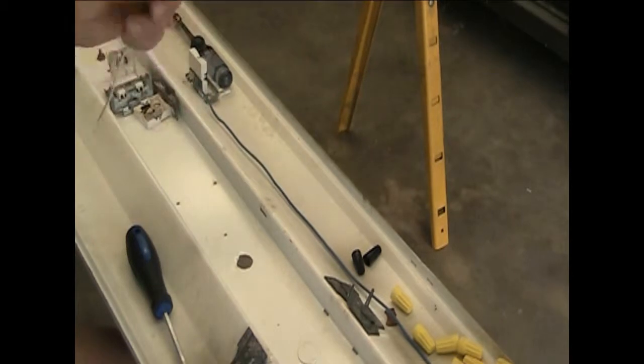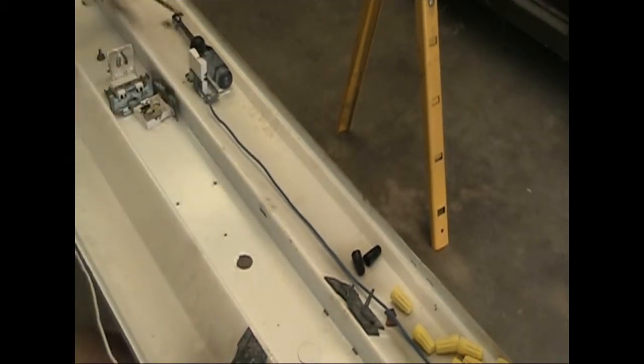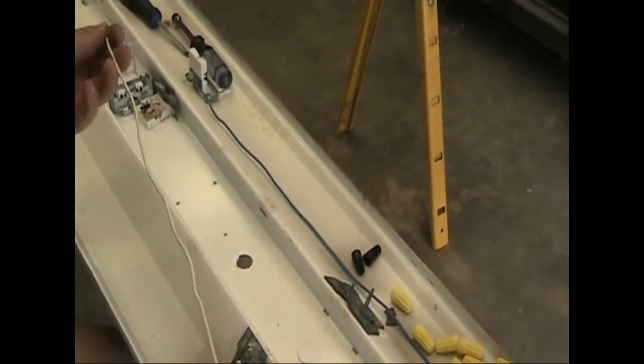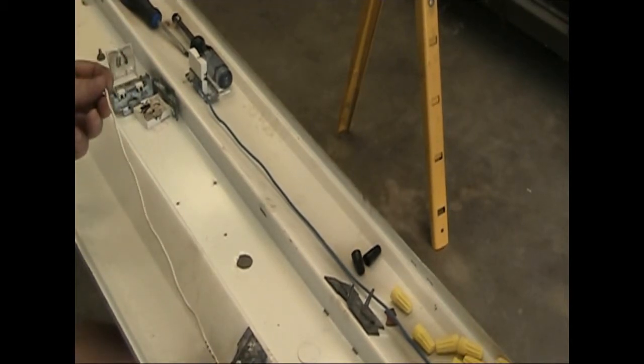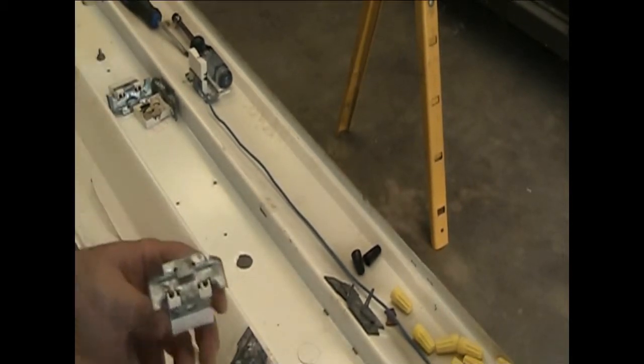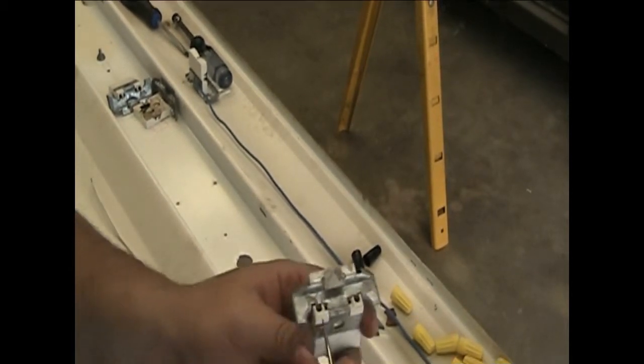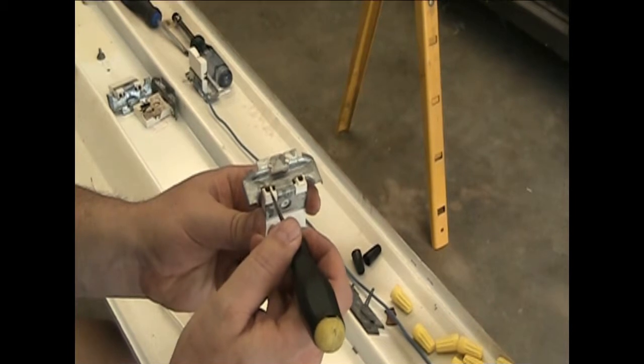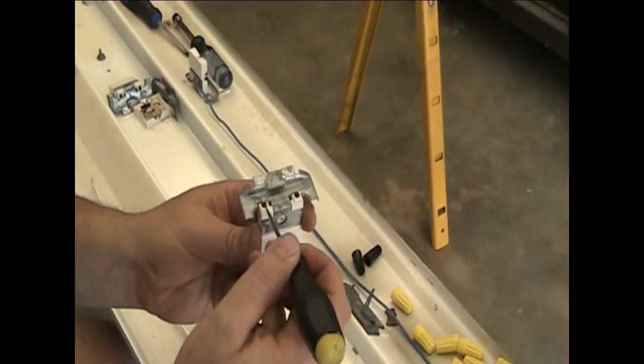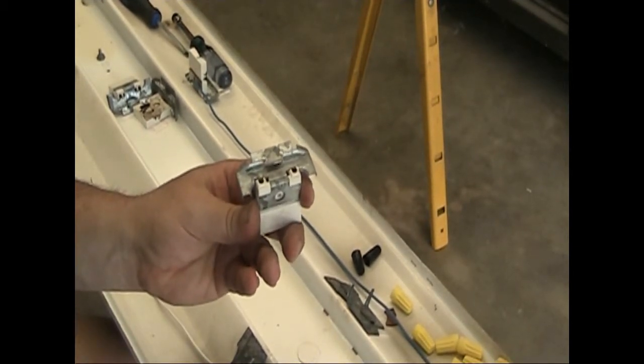But first of all, with the white wire, we're going to make jumpers. And I've done this earlier on another light. So I already know that each of my jumpers need to be approximately two and a half inches long. So I need eight of these because I've got to jump a wire from here to here. I need to jump a wire from here over to here. So that's what I'm going to do. I'm going to cut out eight of them, strip them back, and start putting the wires in these sockets.